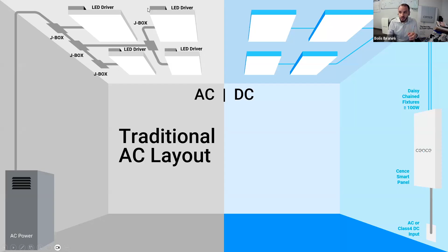So you avoid difficult maintenance. Sometimes these devices are inaccessible, and they're usually the first point of failure. For LEDs, as an example, because it's the market with the most traction right now - typically, if you see an LED flicker or shut off, that's not a failure of the luminaire, the light engine, or the LED. That's a failure of the driver.